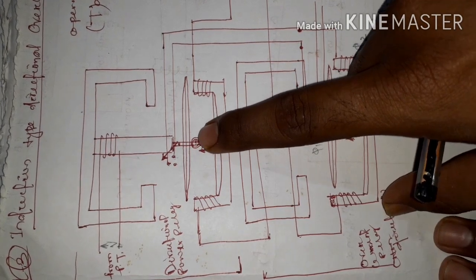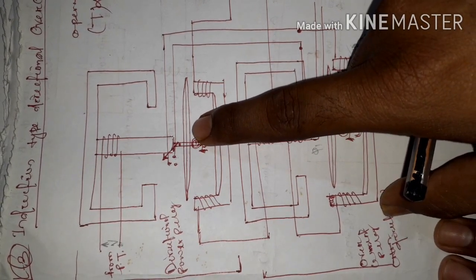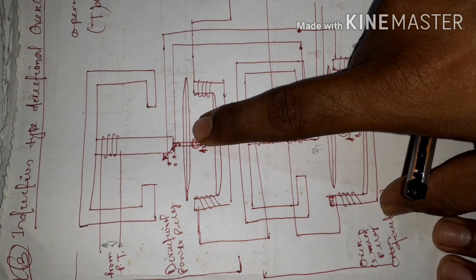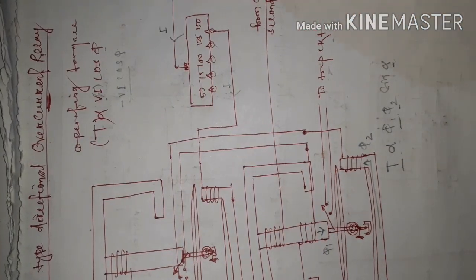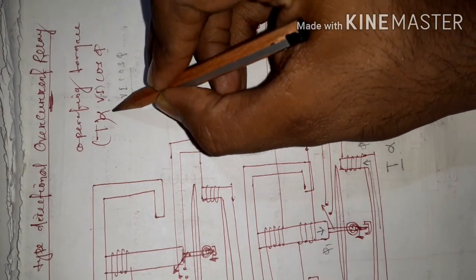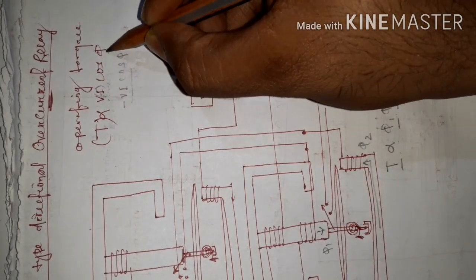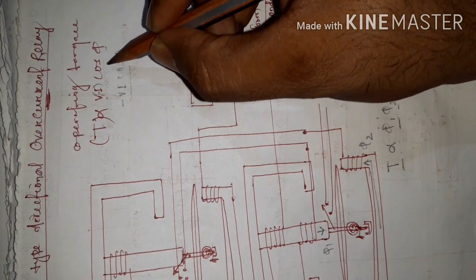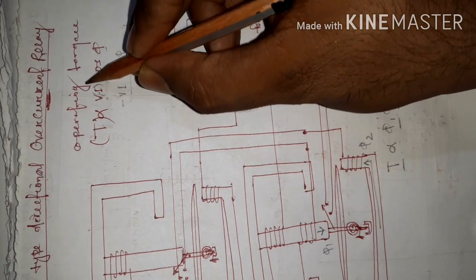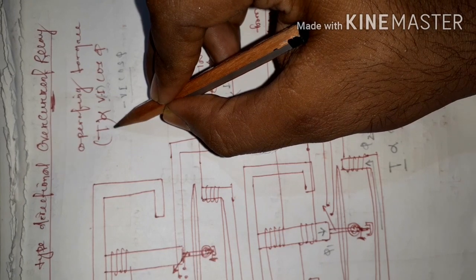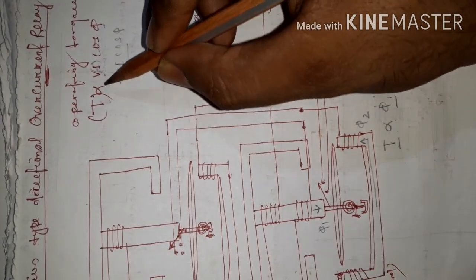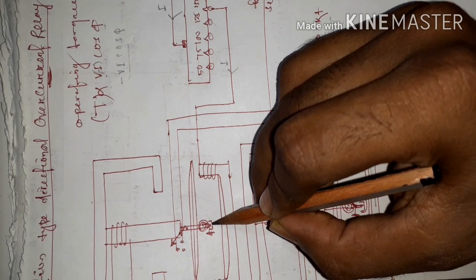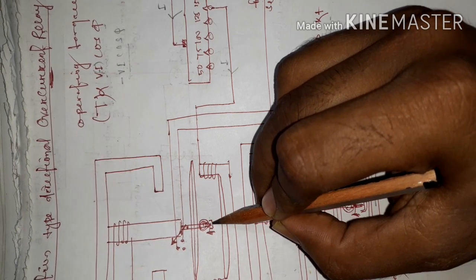The operating torque developed in the upper half, that is the directional power relay, can be written as T is proportional to VI cos φ, where φ is the phase angle between voltage and current. Under normal operating condition this operating torque is positive and is less than the restraining torque provided by the spiral spring.